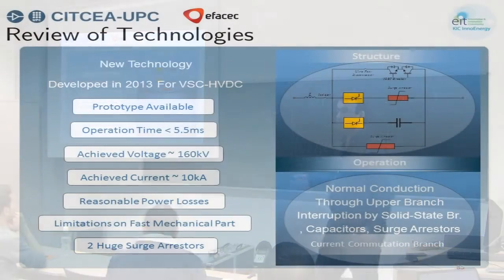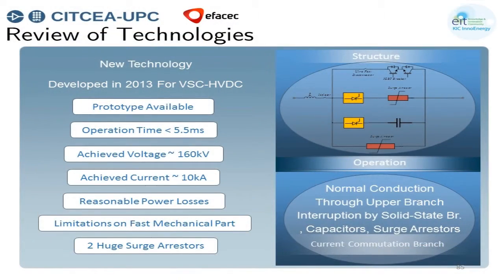So you have another technology, mainly I think it's from Alstom. The concept is almost the same as the previous one. But instead of having the full solid state branch relying on IGBTs and having the surge arrestor in parallel with that only, you will have the main branch, and then you will have thyristor based dampers, and finally another surge arrestor here.